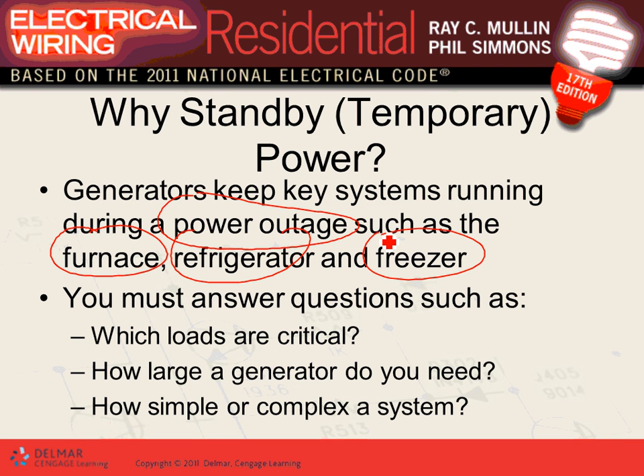You must answer the question, which loads? Now, these are the so-called critical loads. So first you pick the critical loads, then of course another critical load gets a couple of lights. You have to have a lighting circuit. Like if you have a two-story house, you have to have at least one circuit and one light on every story that is backed up by the generator. So you have light on every story, okay?